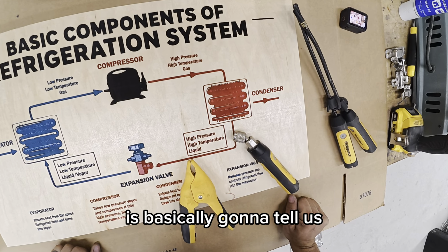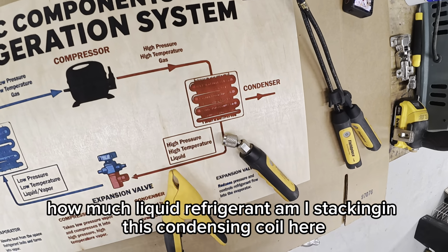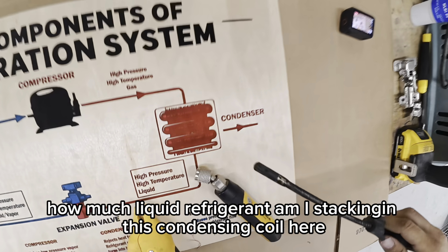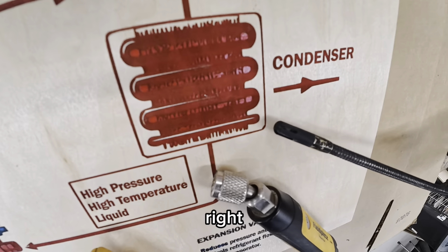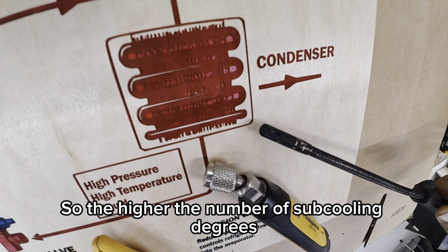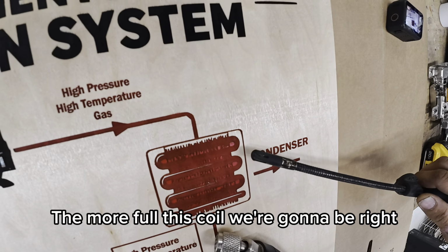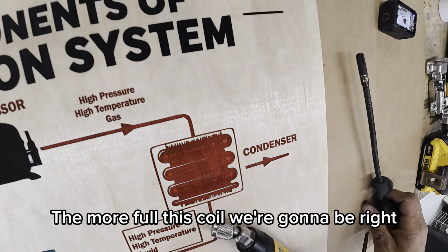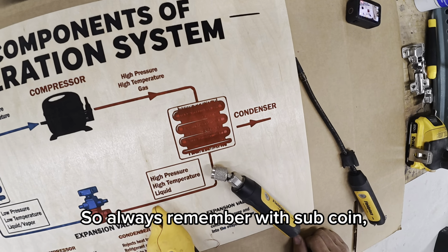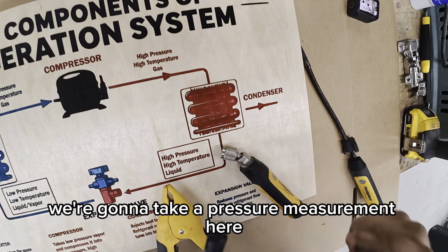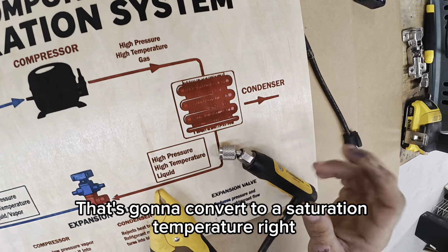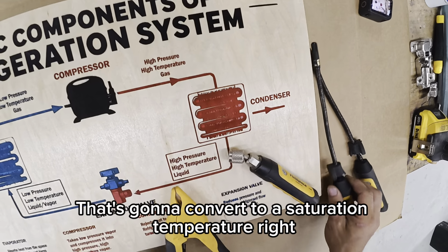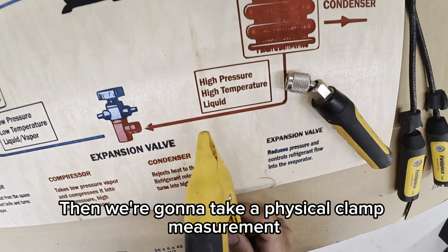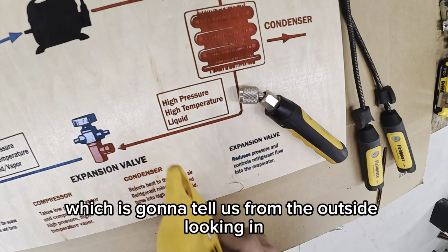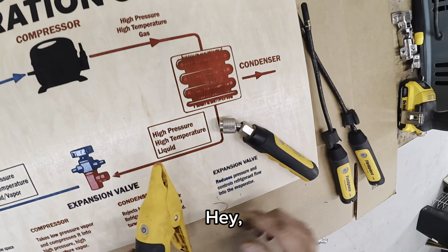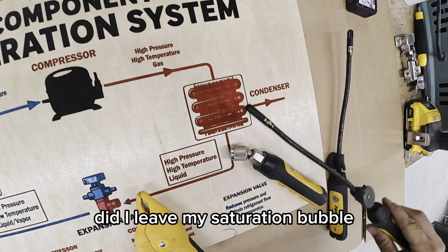Subcooling, right, is basically going to tell us how much liquid refrigerant am I stacking in this condensing coil here, right? So the higher the number of subcooling degrees, the more liquid, the more full this coil is going to be, right? So always remember with subcooling, we're going to take a pressure measurement here. That's going to convert to a saturation temperature, right? Then we're going to take a physical clamp measurement, which is going to tell us from the outside looking in, hey, did I leave my saturation bubble, right?